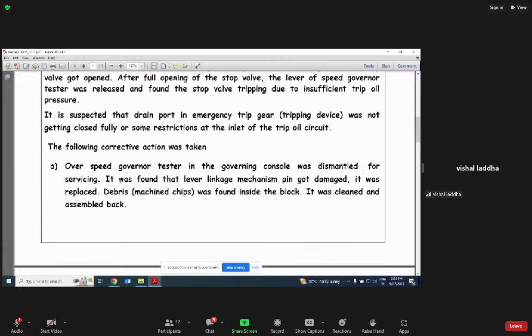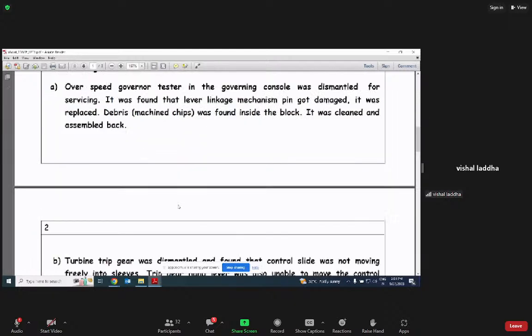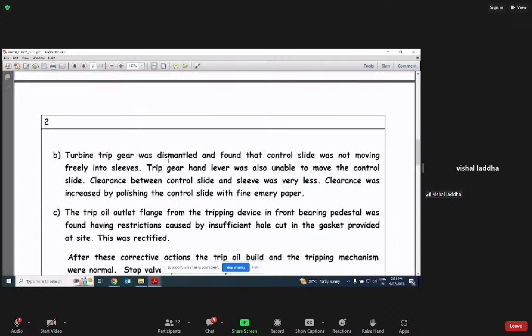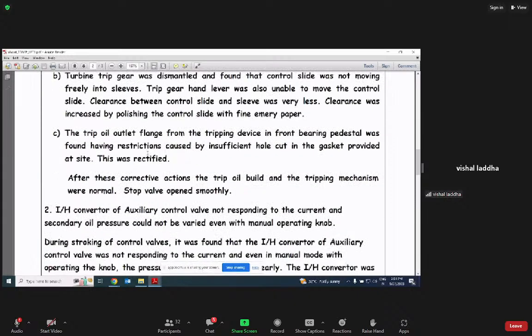For servicing, it was found that the lever linkage mechanism pin got damaged. It was replaced. Debris was found inside the block. It was cleaned and assembled back. The turbine trip gear was also dismantled and found that the control slide was not moving freely in the sleeves. The trip gear hand lever was also unable to move the control slides. Clearance between control slide and sleeve was very less. Clearance was increased by polishing the control slide with fine emery paper with the help of the mechanical team.